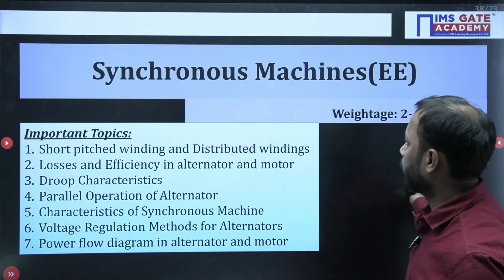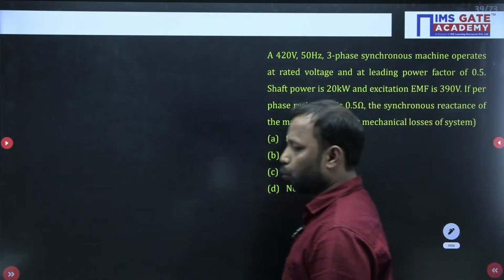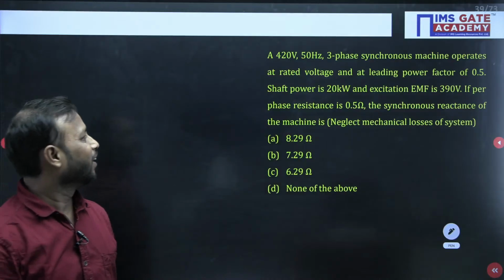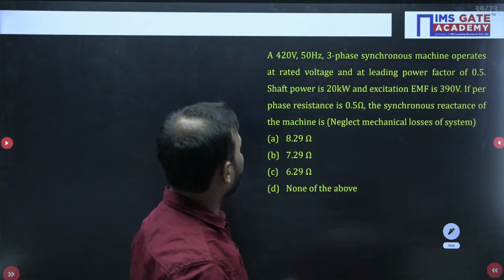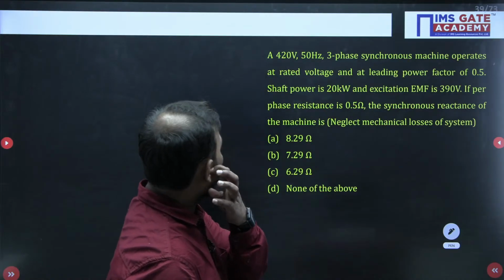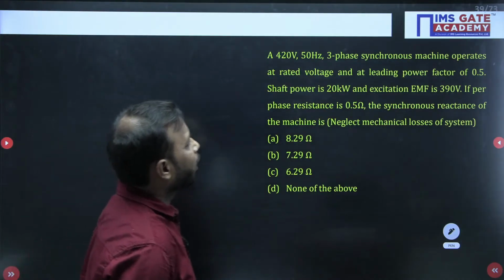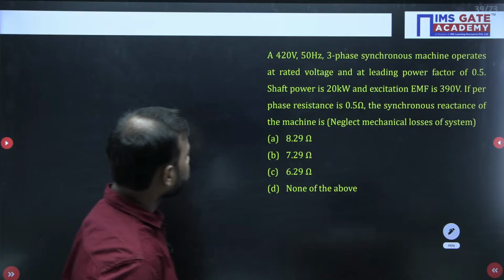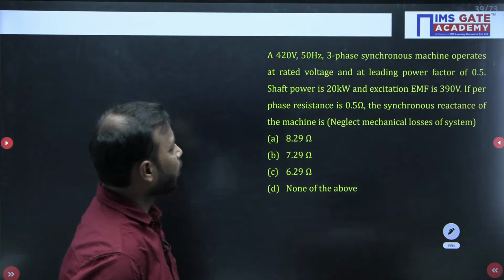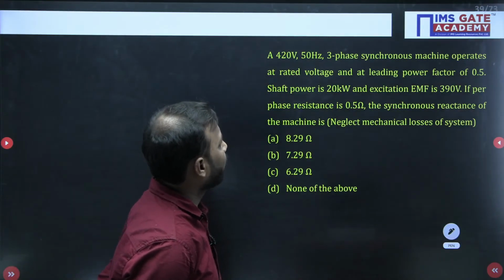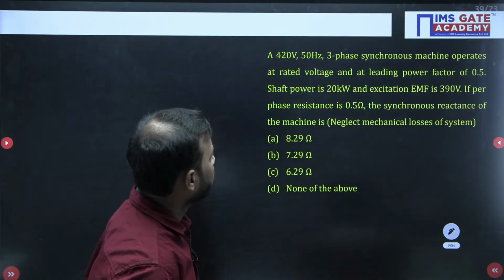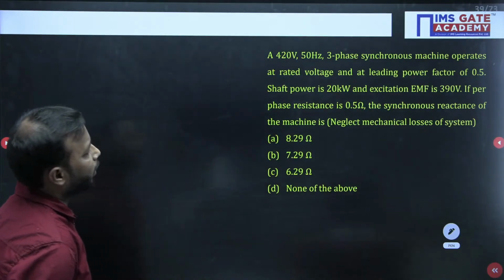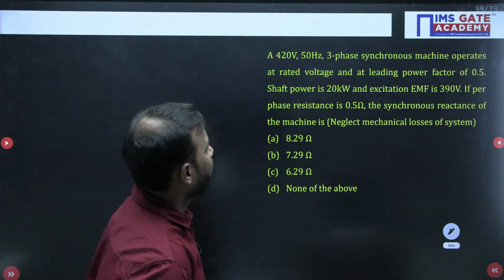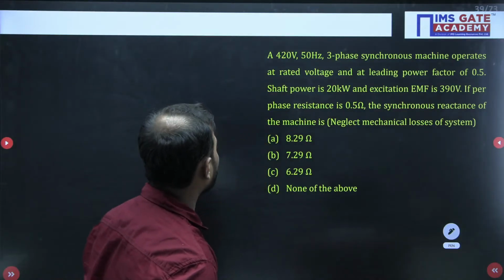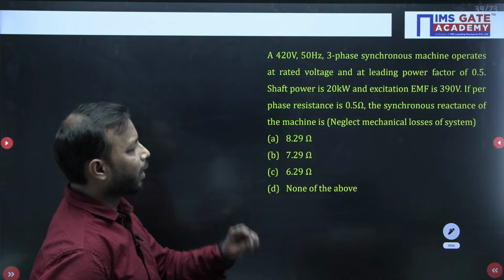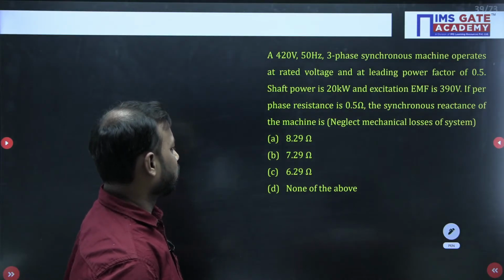All right, let us directly move to question number 1 under the synchronous machine. A 420 volt, 50 Hz, 3-phase synchronous machine operates at rated voltage and at a leading power factor of 0.5. Shaft power is 20 kilowatt and excitation EMF is 390 volt. If per phase resistance is 0.5, find the synchronous reactance of the machine. Neglect mechanical losses of the system.